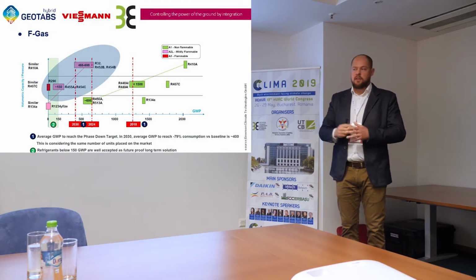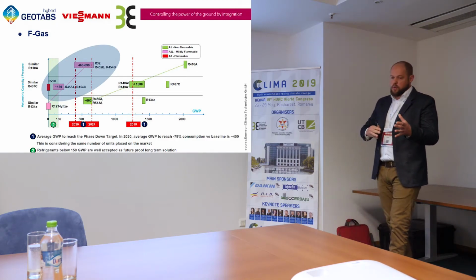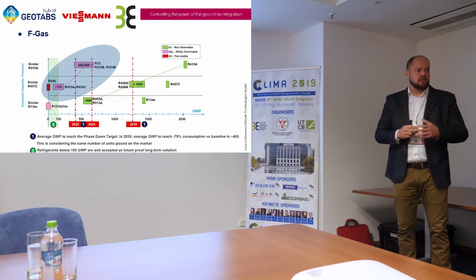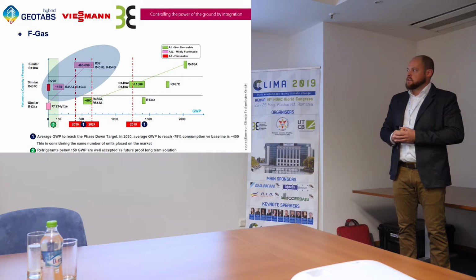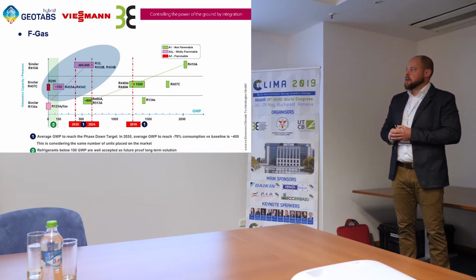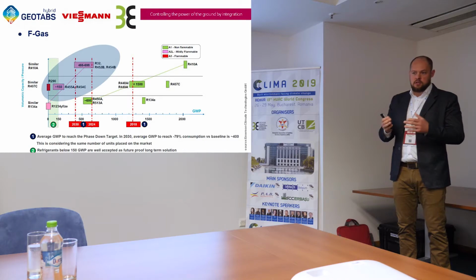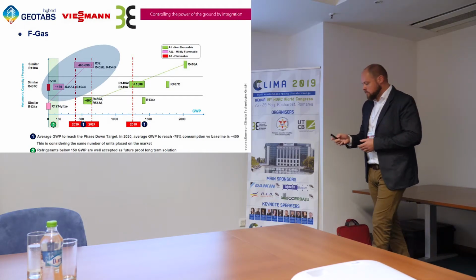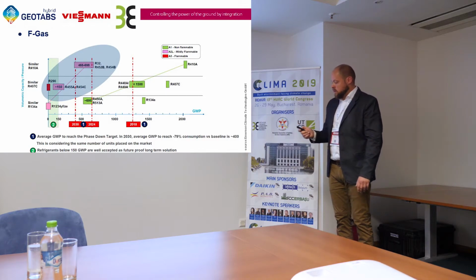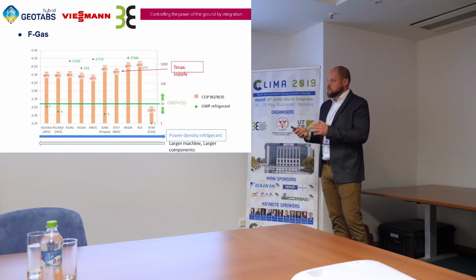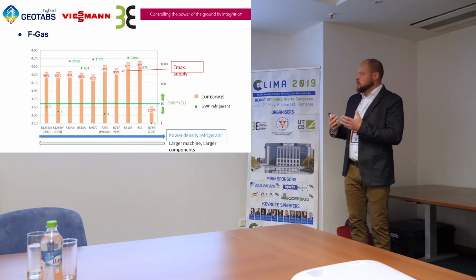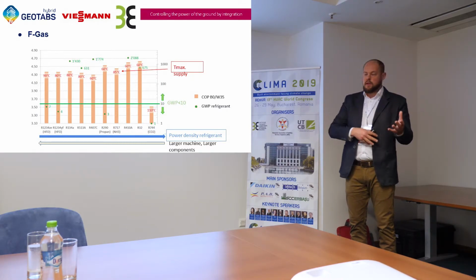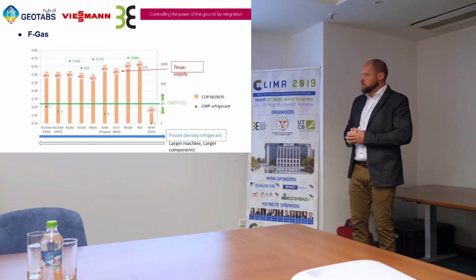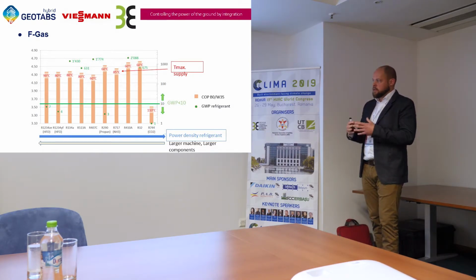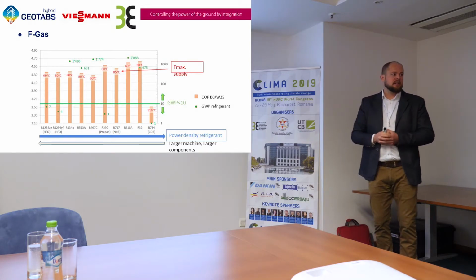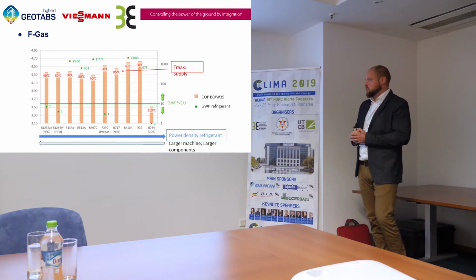So in the future, when we have a need for high temperatures, and we have a waste heat source of about 40-50 degrees, we can reuse that waste heat to make a very high temperature and supply another industrial process or a heating demand in a building. So this is quite a challenge, because what we also see with the different refrigerants, the refrigerants we use today we know very well. We know the components we use, the compressors, the evaporators and so on. But when we use more natural refrigerants or other refrigerants, we have to adapt also the refrigerant cycle inside the heat pump to work with these new refrigerants.